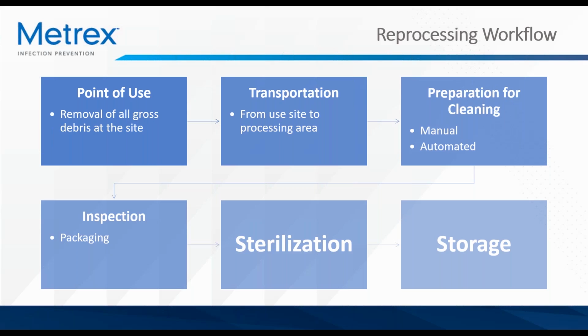This can be done manually at a sink, or this can involve an automated washer. Next step in the workflow after cleaning is inspection, which also involves packaging the items for either sterilization or preparing for terminal high-level disinfection, depending on the device classification. The reprocessing workflow ends at storage, making sure instruments are stored appropriately for future use.